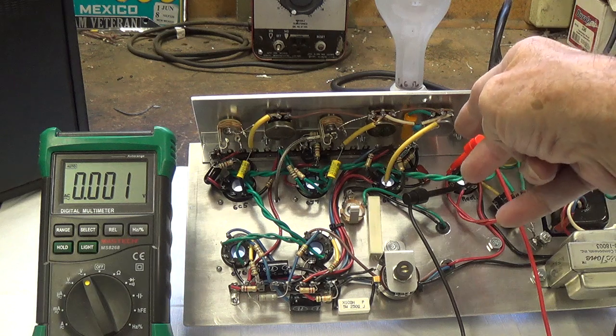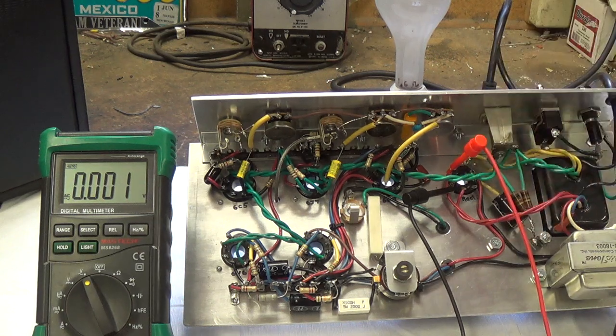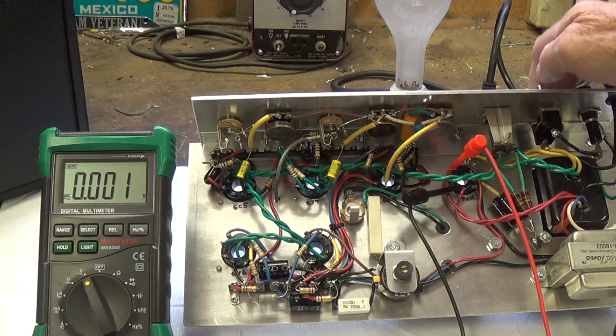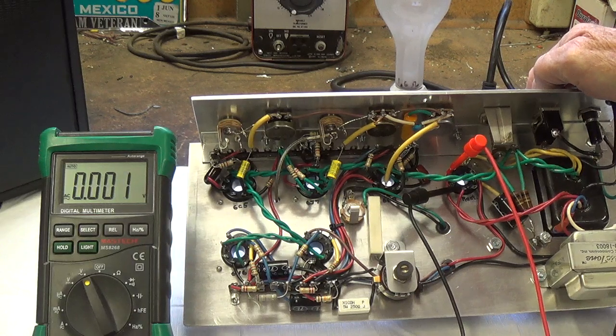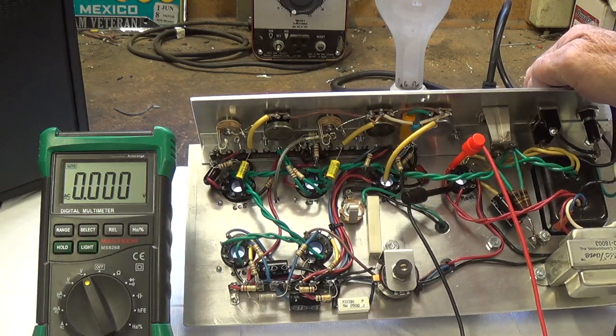Next, we're going to hook up between pins 4 and 6 of the rectifier. This will be the high voltage output from our transformer, and it's going to be sky high, because there's no tube in place it may be beyond the measuring capability of your meter. Let's see what happens.